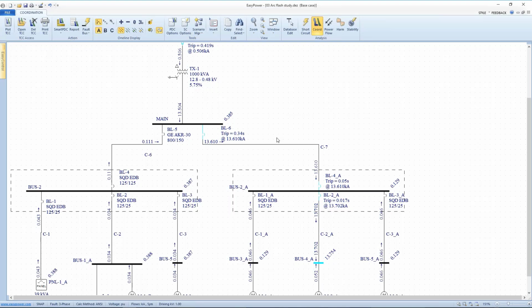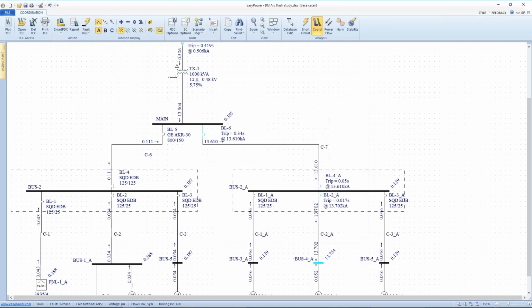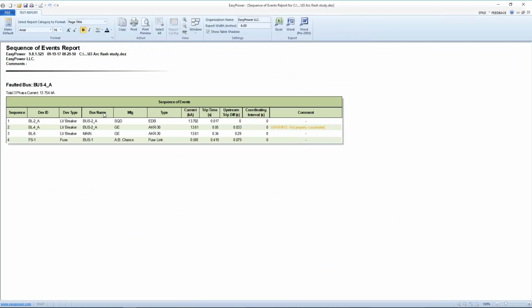So at that point I've checked my sequence of events, and I'd want to do that across the board. The tool allows me to say, well, that's nice. How about showing me a sequence of events report? And if I come back here and fault this bus again, my little report shows up. And now I can see that I have separation between each of the buses, and it'll give me a warning when things aren't properly coordinated.